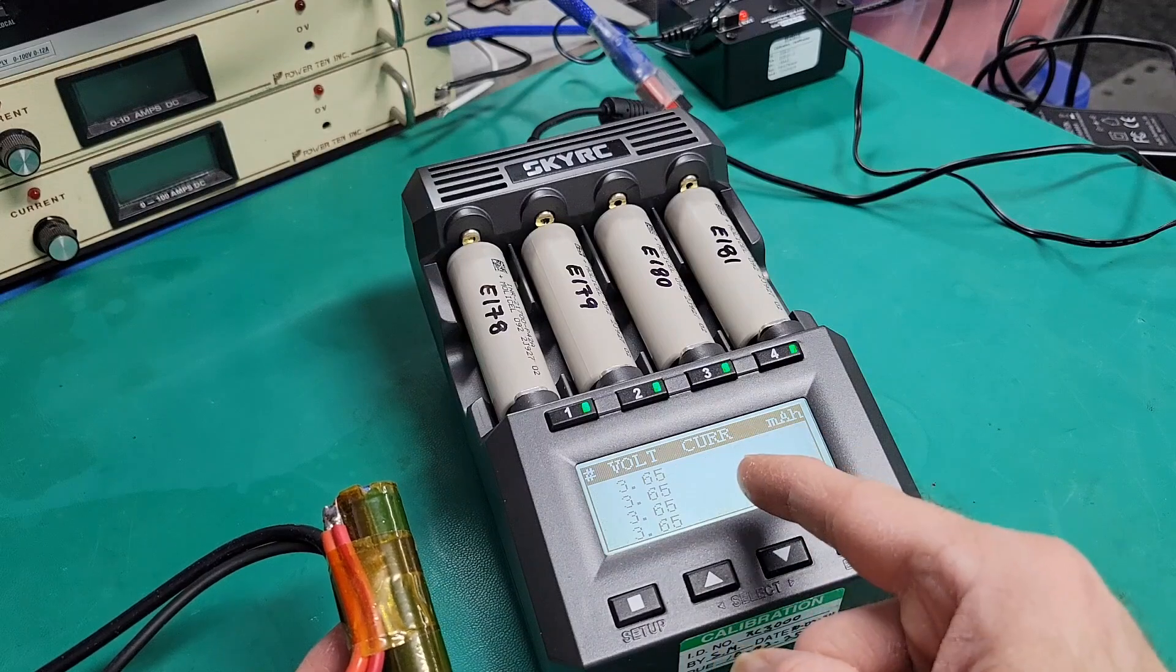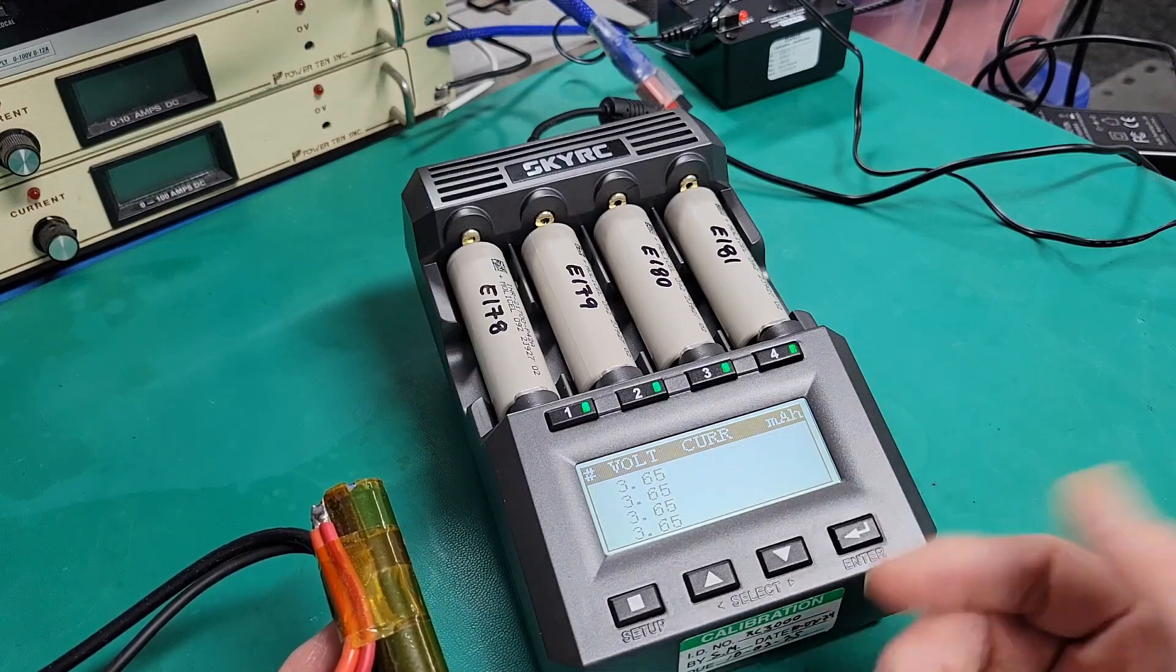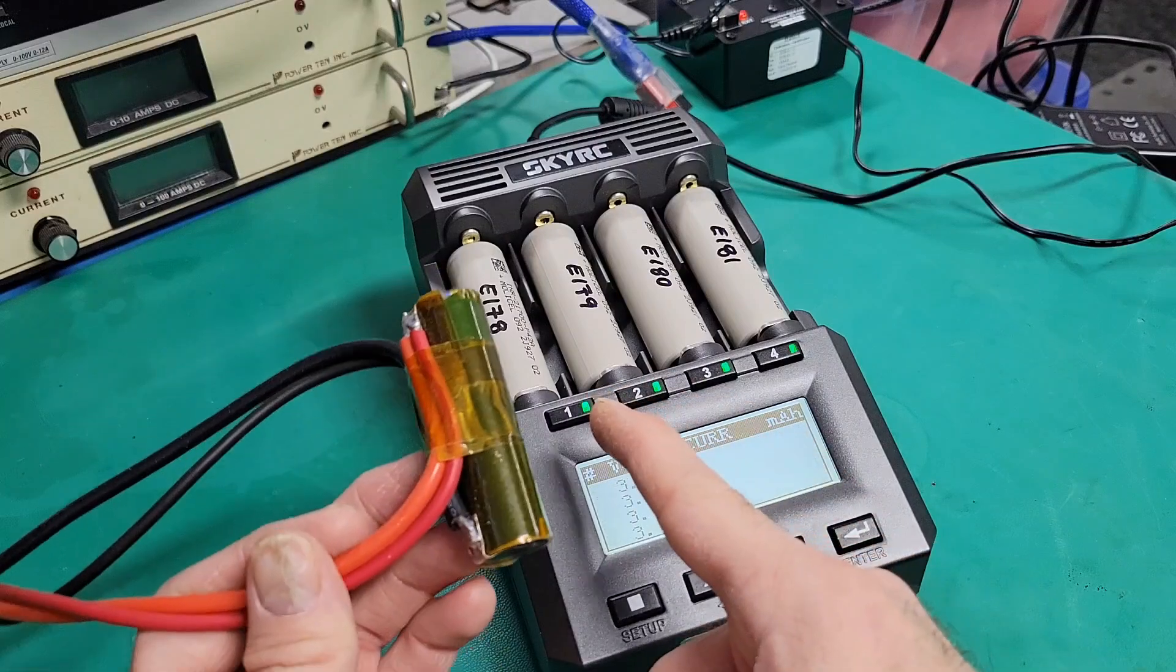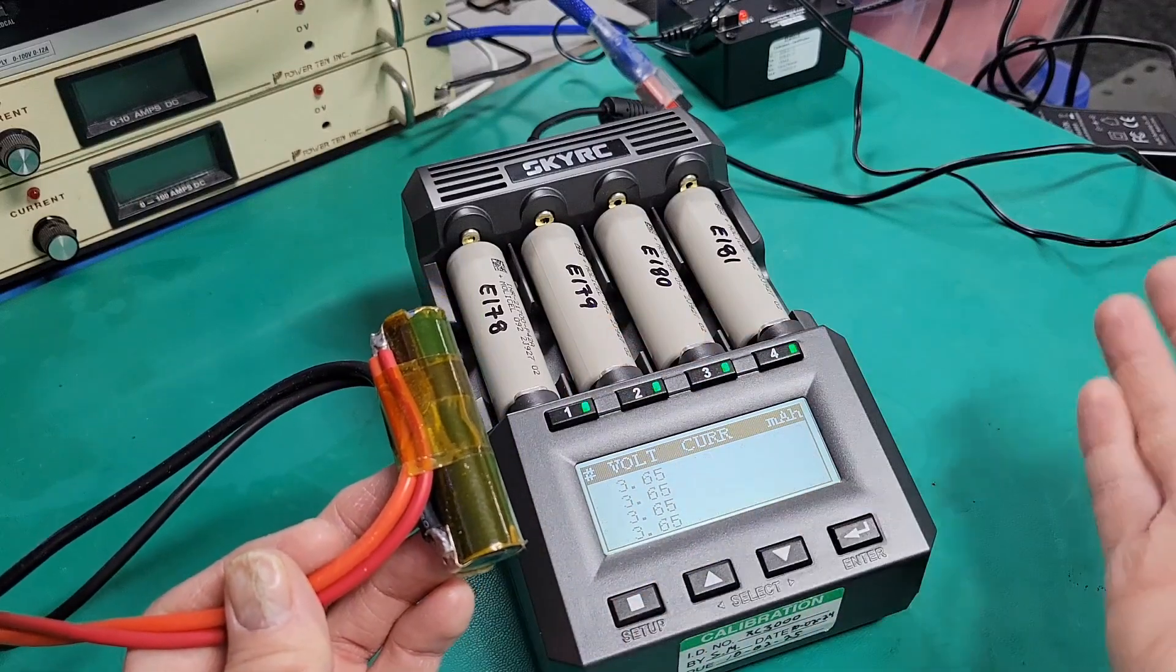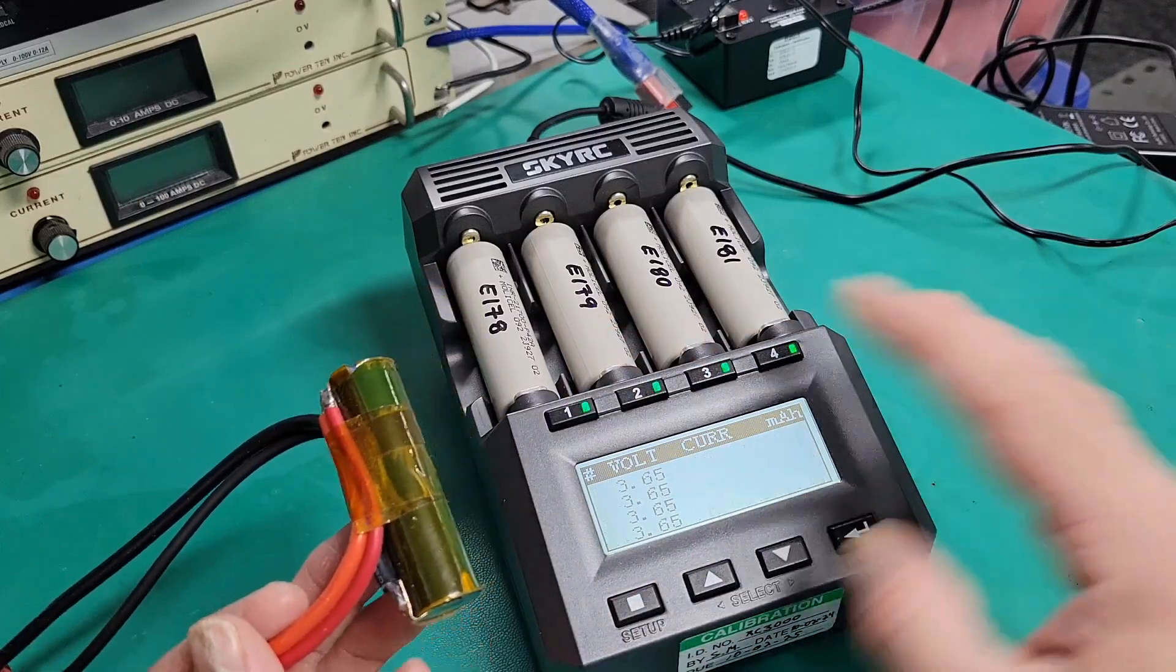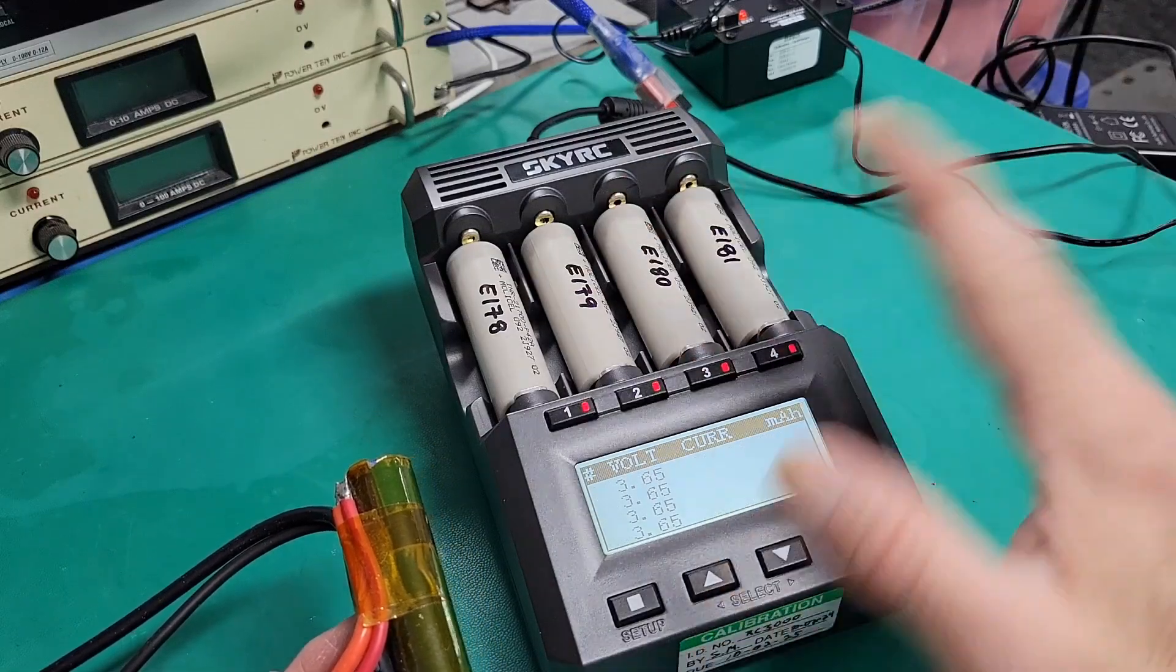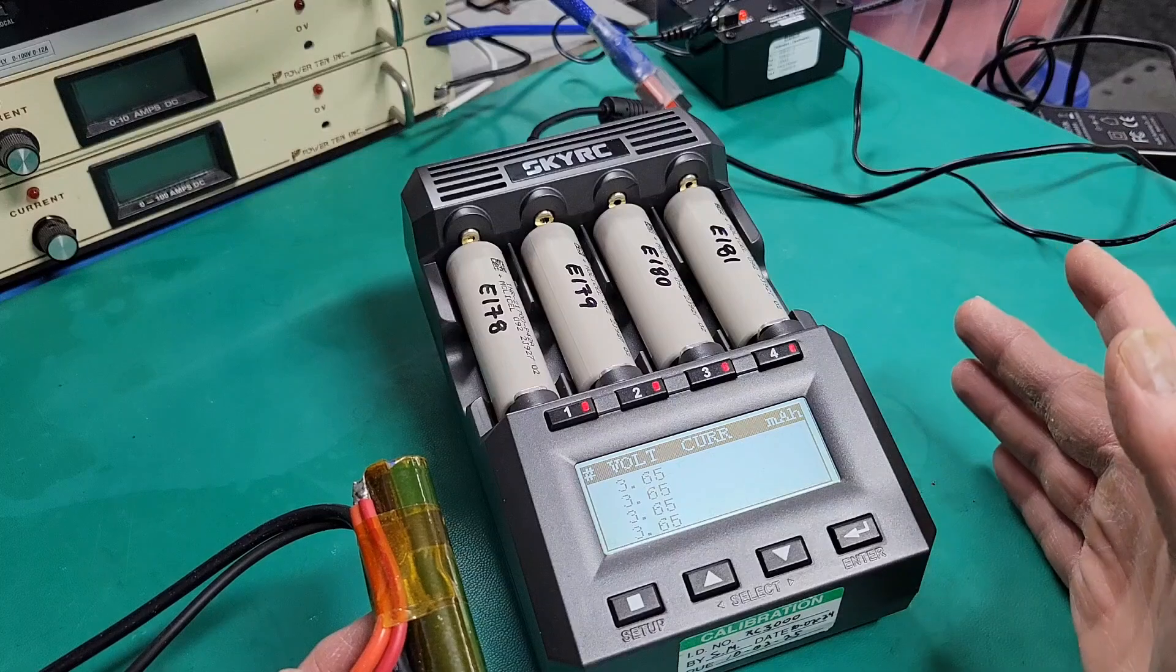And if this one is off, I can compensate until it's reading the right value. And I can do that with all the same four channels. So if I can do that for the four channels, I know that if I measure a cell with this channel or this channel, they will all read the same. And that is very important.